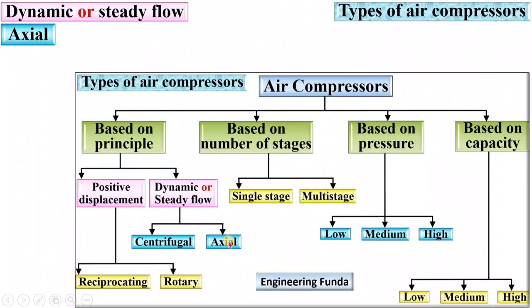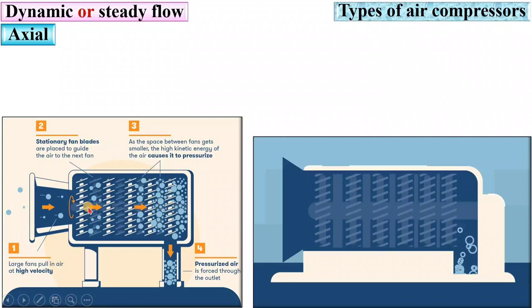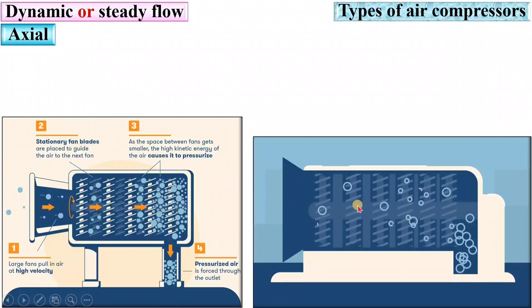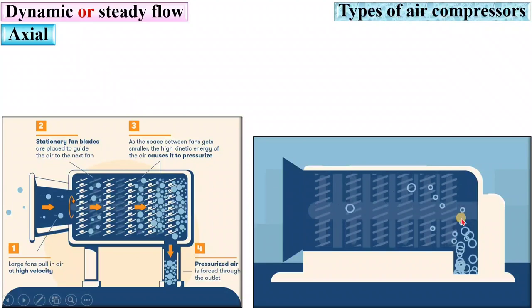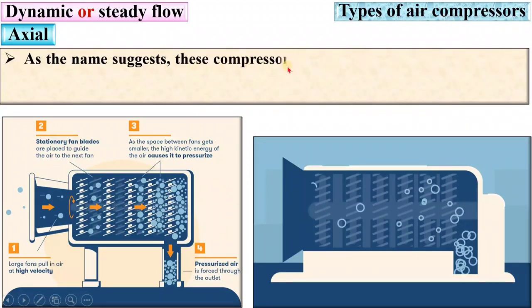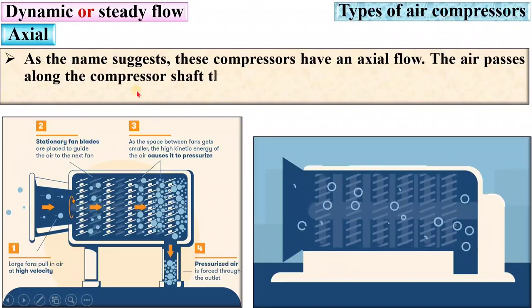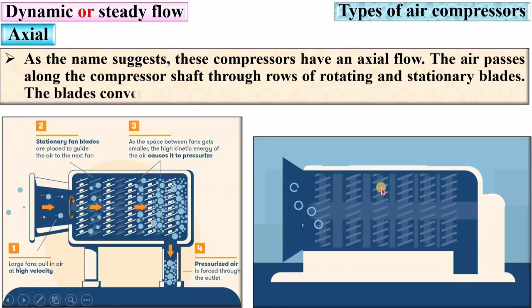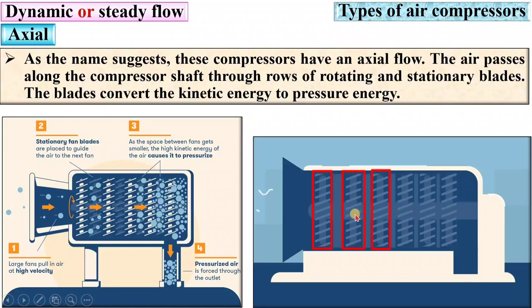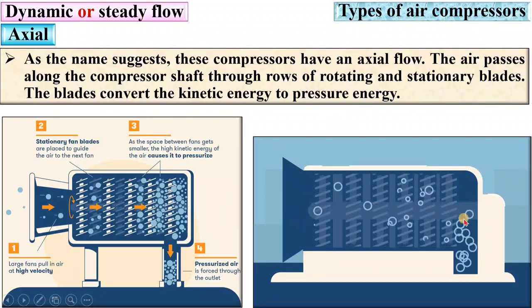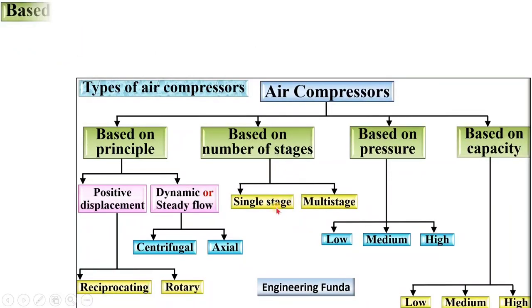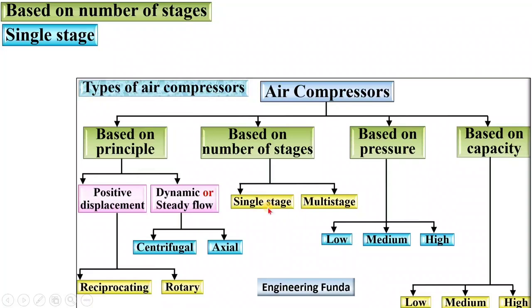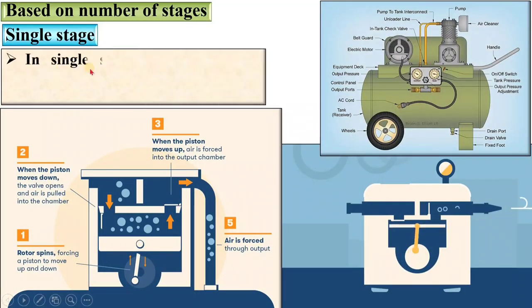Next, axial compressor. The flow is in the axial direction — that is why it is called an axial flow air compressor. The air flows along the axis of the compressor. As the name suggests, these compressors have an axial flow: the air passes along the compressor shaft through rows of rotating and stationary blades, and the blades convert kinetic energy into pressure energy.